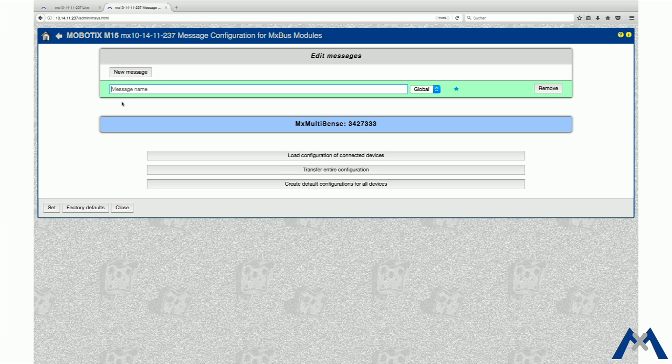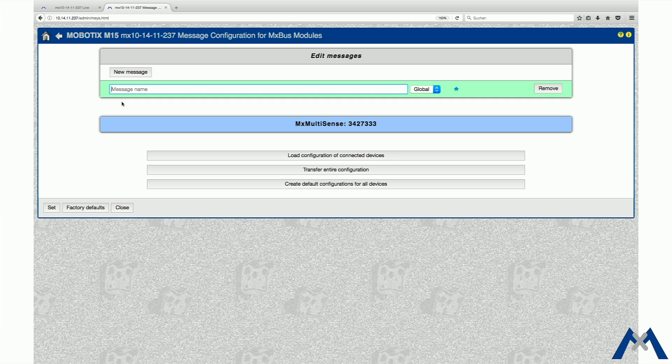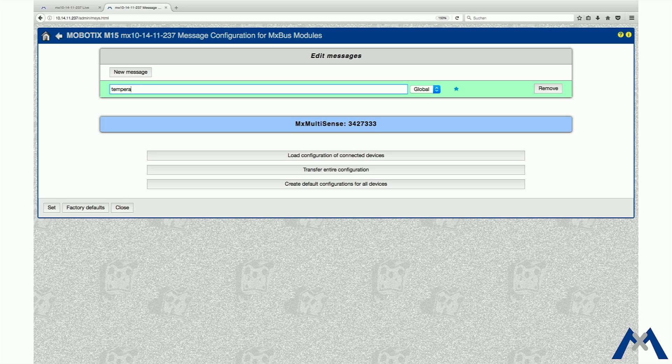Imagine the following scenario: the monitoring of the temperature in a server room should be realized using the Multisense. If the temperature reaches 35 degrees Celsius, a warning message should be sent out. Therefore, the message Temperature Warning is established. Make sure the names of the messages are explicit so correct and easy allocation is given.